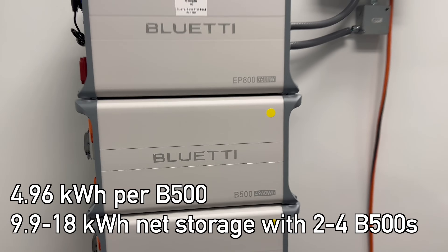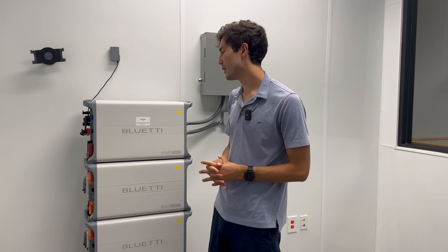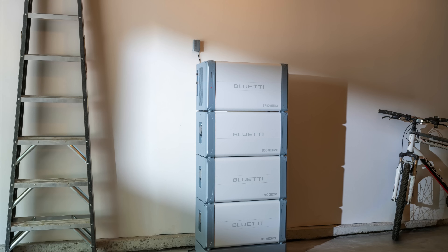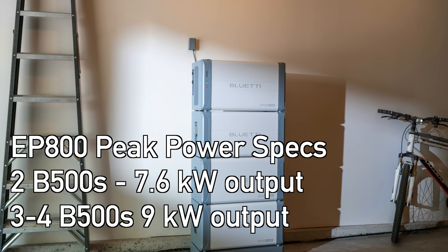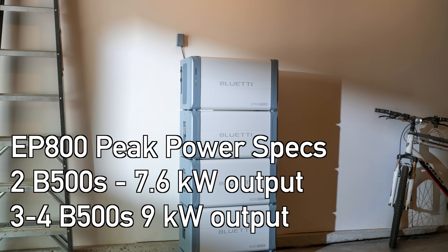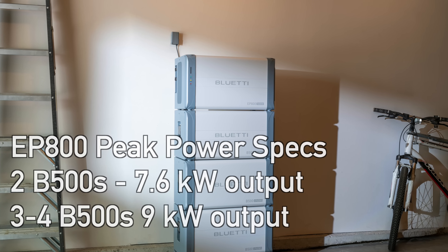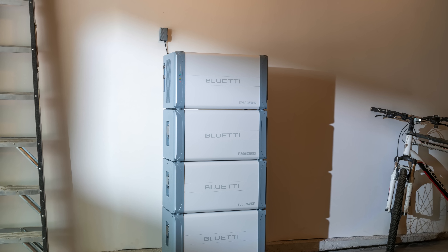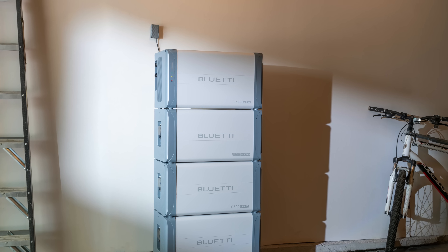These have 4.9 kilowatt hours of capacity. Net capacity when you use two of them would be nine kilowatt hours. But if you stack four of them, which you can go up to, then you have 18 kilowatt hours of energy reserve. Bluetti says that two of the B500 batteries can be used with the EP800 to give you 7.6 kilowatts of power output. And they claim if you've got three or four of them, you've got nine kilowatts of power output from the system, which is plenty to fuel all kinds of appliances — microwaves, fridges, washing machines, other high voltage appliances like an electric car. You can charge that comfortably with a system like this and have that energy either for emergencies or, as I'll talk about later in this video, load shifting.